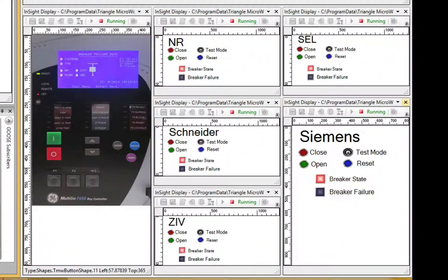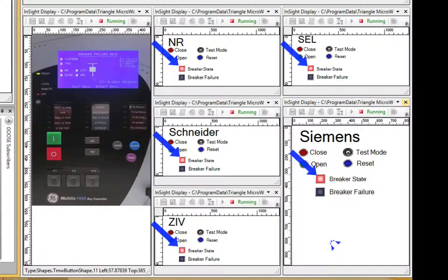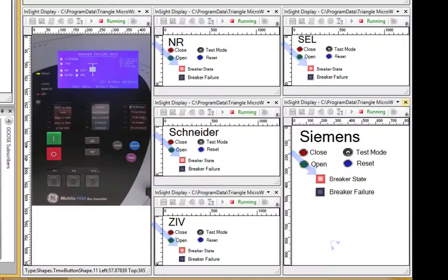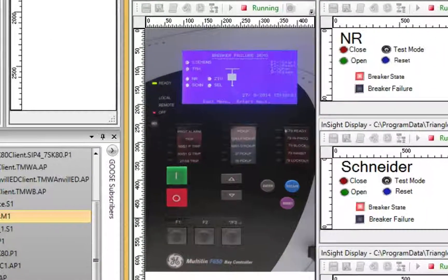If we look at each of the device displays in DTM, we see that the breakers are closed, as indicated by a red breaker state. On the GE device, the front panel shows the closed breaker and none of the fault indicators are lit.